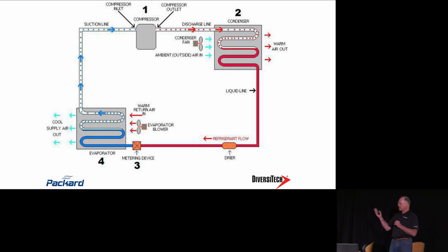So we use fans on the condensing units. How about on the evaporator side? Do we use fans or do we use blowers in refrigeration? Fans. But don't we use blowers in HVAC? So we use fans on the condenser side for both the refrigeration and HVAC applications with condensers, but we use fans in refrigeration and blowers in HVAC.